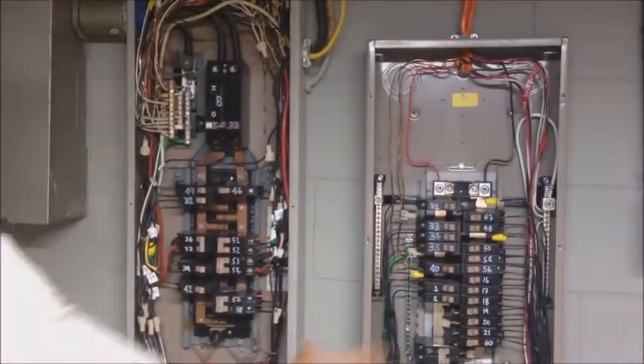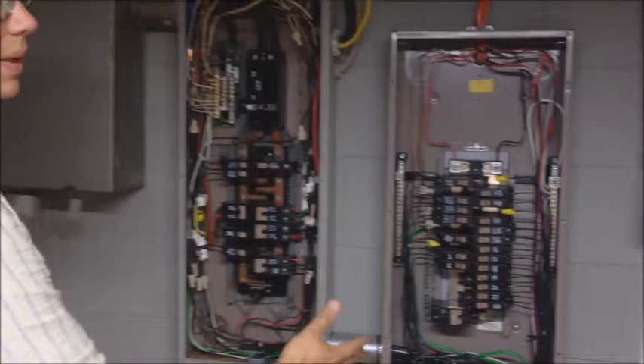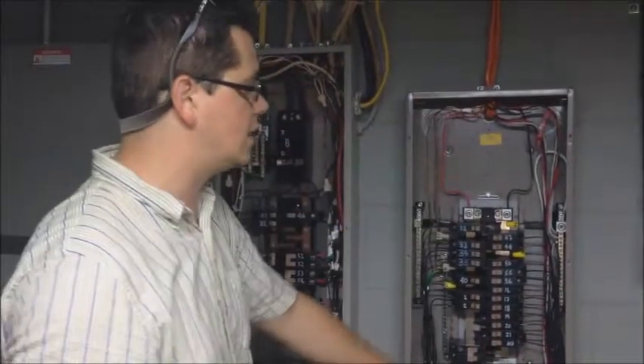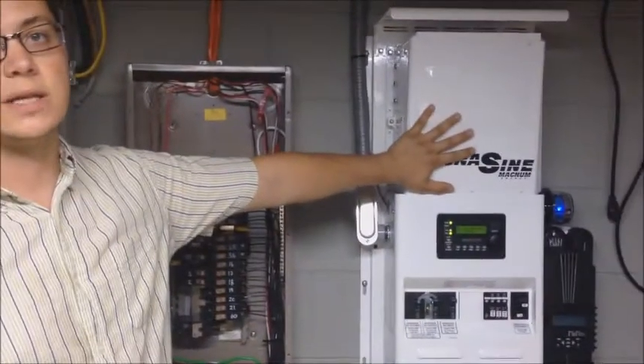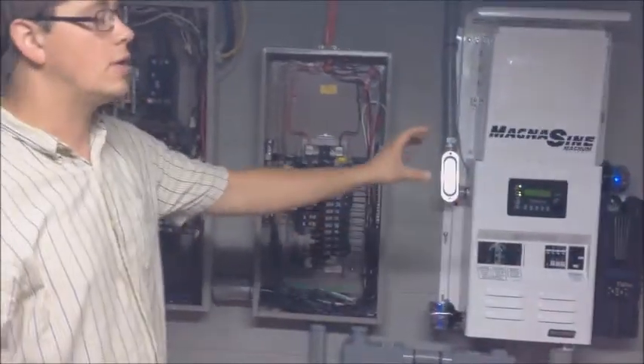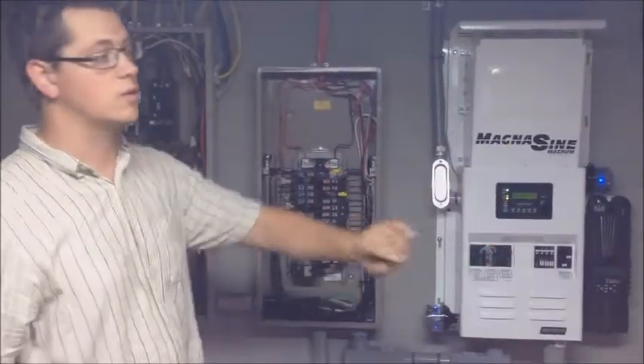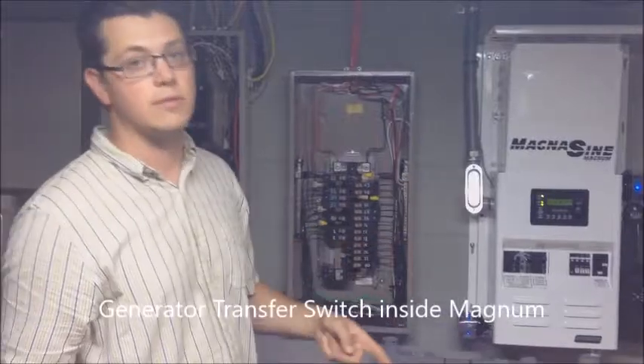So now this is just like a generator sub panel, very similar to the way it goes in, except the transfer switch, the automatic transfer switch is inside the Magnum. So you don't have to get the big automatic transfer switch. We're actually feeding this thing with a generator as well.